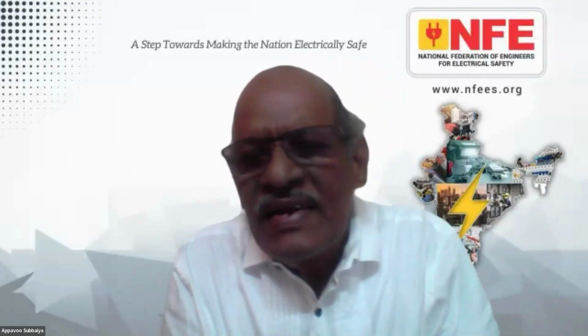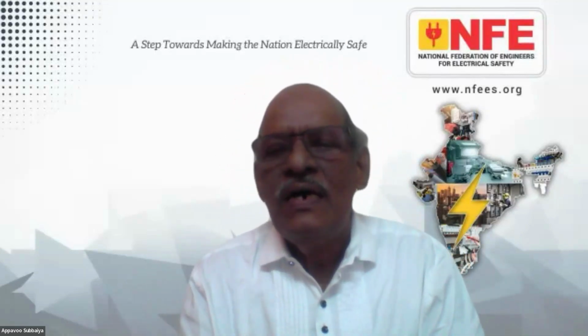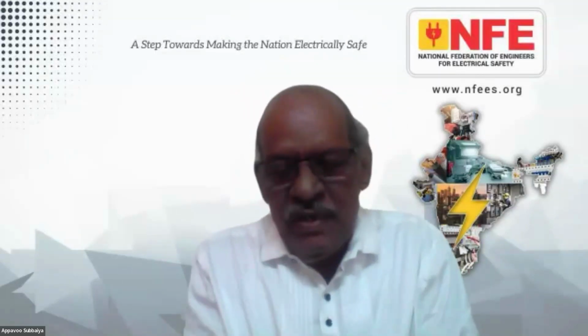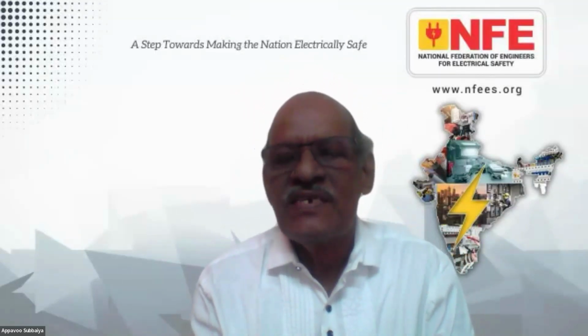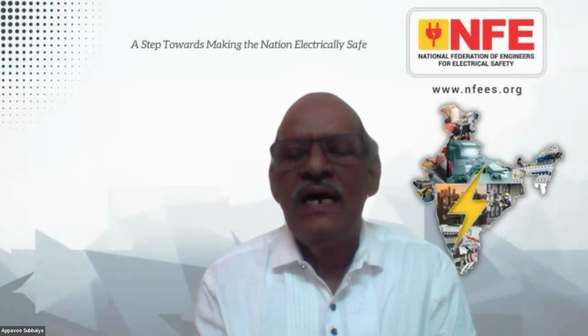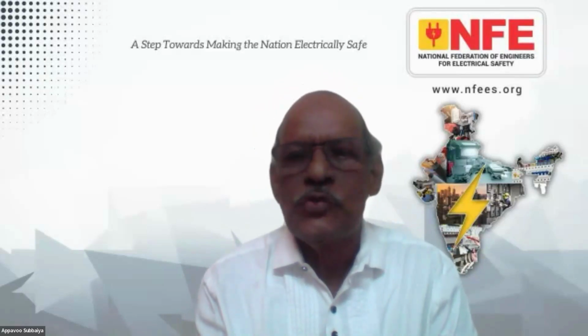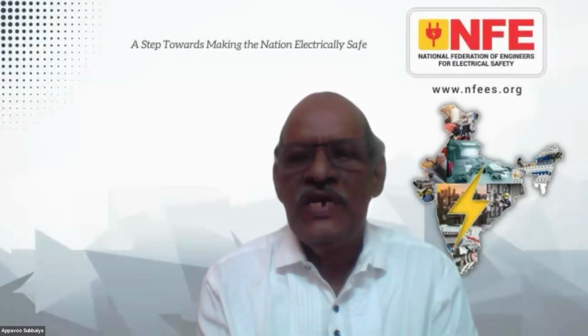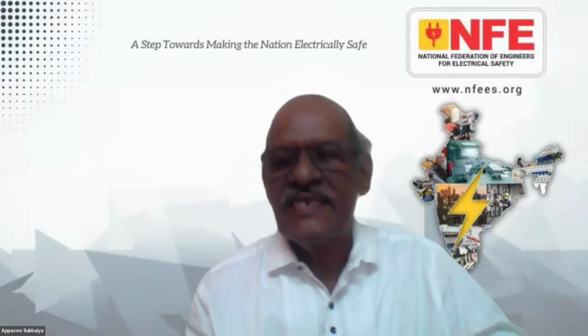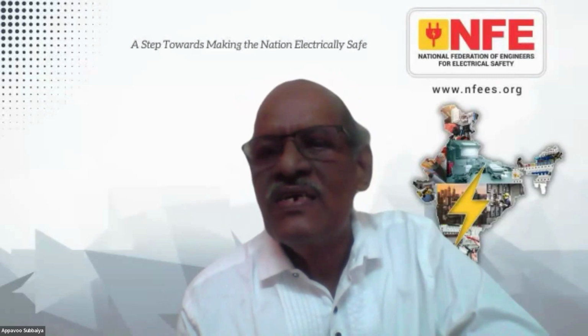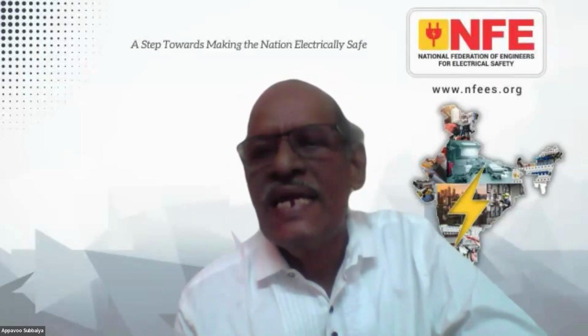Of course, he can test it using earth loop impedance. He doesn't have a right of way, whether the PME is there, whether the interconnection is there, whether the earthing is there. These are all beyond the scope of consumer. So consumer has to do his part of compliance and supplier has to do his. As you said, sir, for detailed discussion, we have on our website and our NFE YouTube channel lot of deliberations on this, relating to IEC 61936 Part 1, where it has been specifically stipulated how equipotentiality and interconnection can be achieved with reference to supplier's installation. It deals with a very big subject.